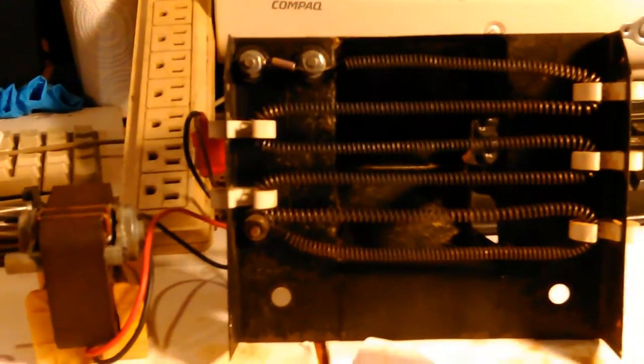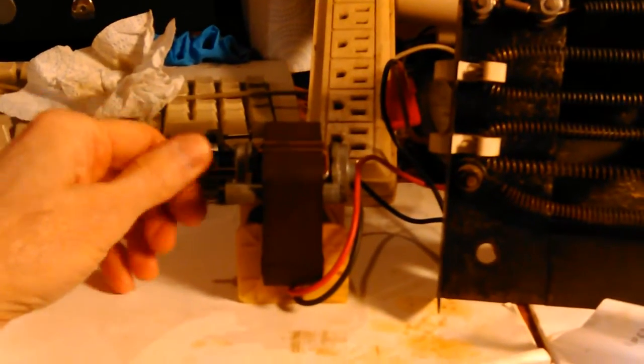I've got the old original motor. I have two of them. See, this is the new rotor and the new fan, which is about two years old. And this is bad. I've confirmed that this has an open circuit in it and it's bad.